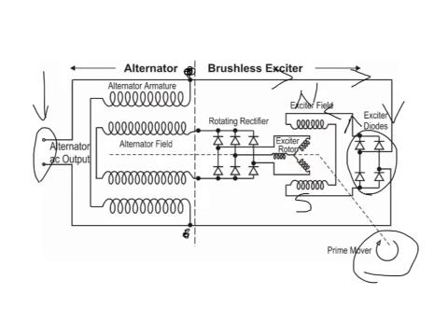Current flows through our exciter diodes, creating a bigger north and south pole which gives us our lines of force. As the prime mover turns the exciter rotor through those magnetic lines of force, an AC voltage is induced onto the exciter rotor. That AC voltage — essentially an electrical pressure — causes AC current to flow out to our rotating rectifier. The rotating rectifier is physically part of the machine, built right on the rotor itself — there are no brushes whatsoever. That AC current is rectified by a three-phase full-wave rectifier, providing a relatively clean DC output.